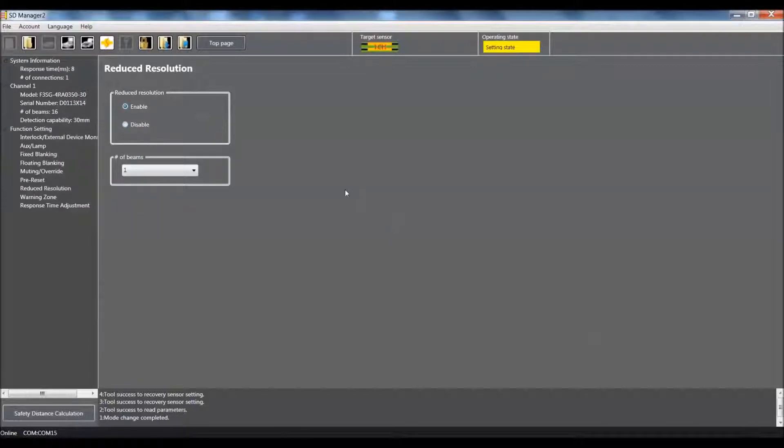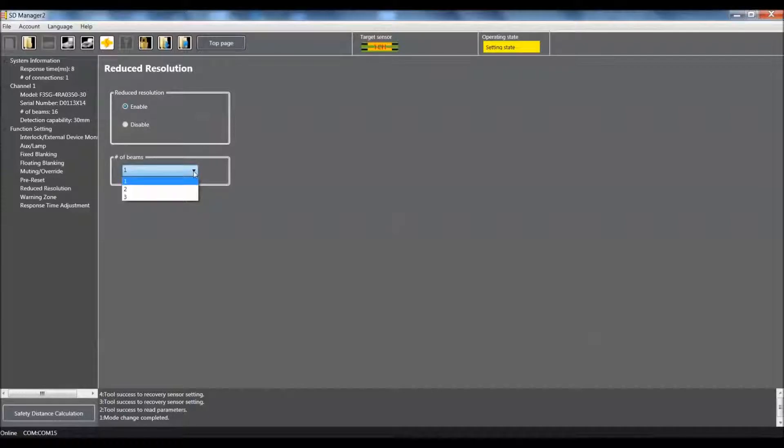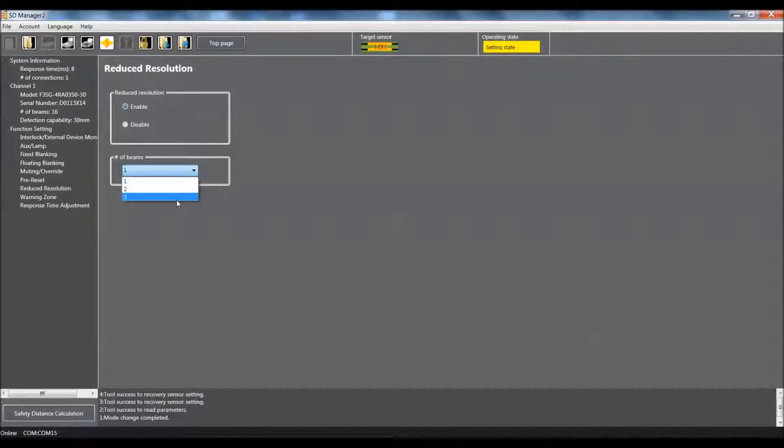And the object that I am going to be using will basically encompass three beams. So that would be our next setting down here, the number of beams. Using this pull down, you have the ability to select between one and three beams. My objects that I am going to be demonstrating with will block three beams. So I will select three in this case.